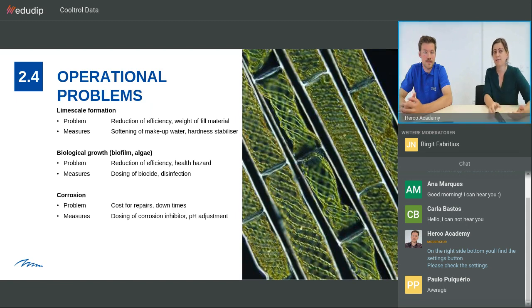Here you can see which operational problems you can encounter in a system. The main three really are limescale formation, biological growth, and corrosion. Limescale formation clearly occurs if we have an elevated concentration of calcium. We are going to get the same limescale you get, let's say, in the kitchen when you heat up water in a pot. This is a problem because of reduction of efficiency, obviously, but also the weight of the fill material, for example. So you can get even a compression or destruction of the fill material if there's too much limescale formation. Solutions or measures taken to avoid this are softening of the makeup water, for example, and in very many cases, the dosing of hardness stabilizer to the circuit.